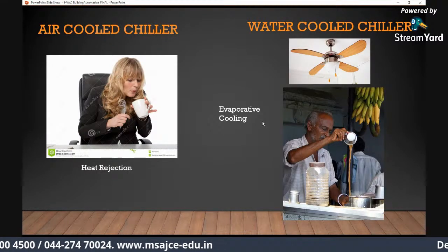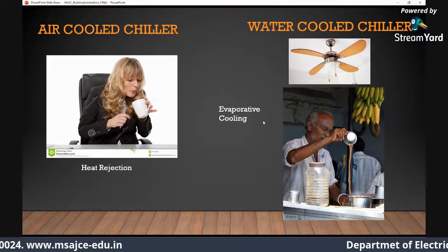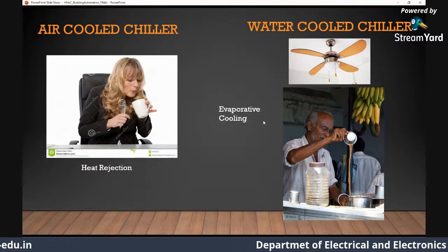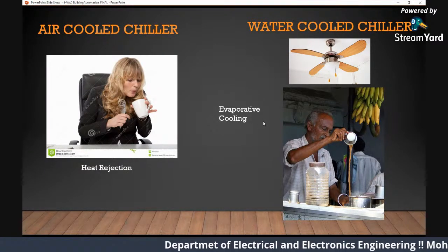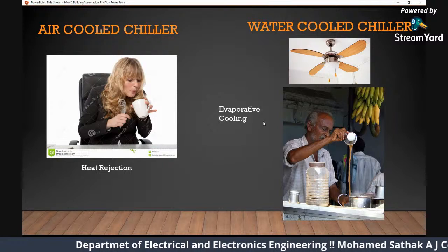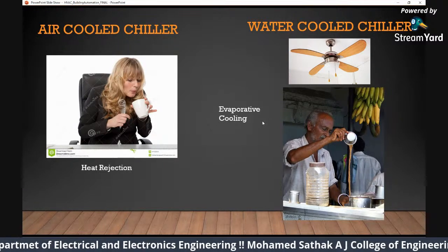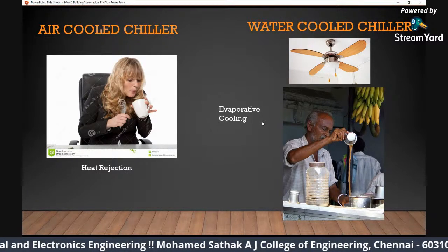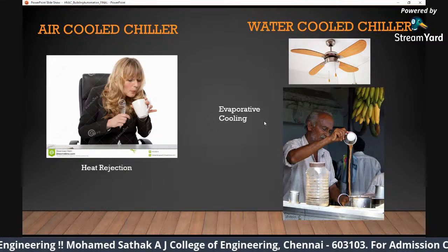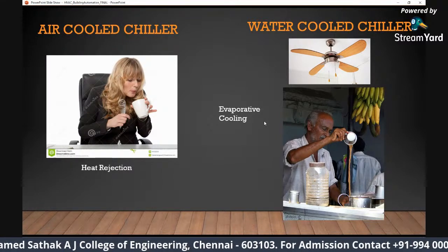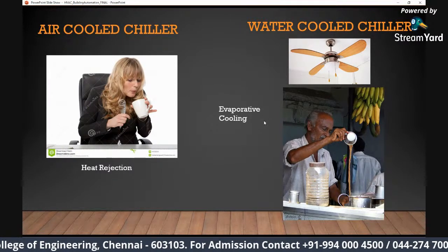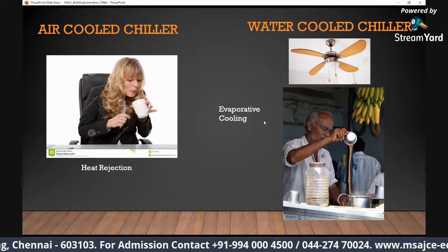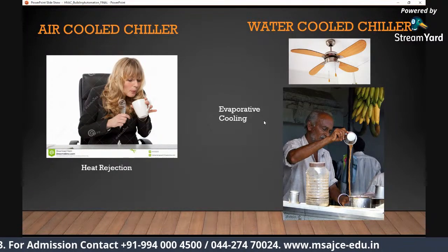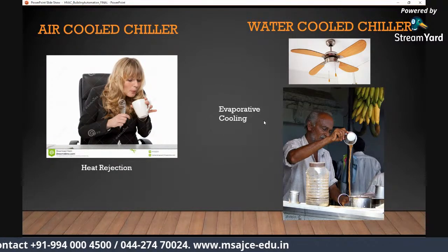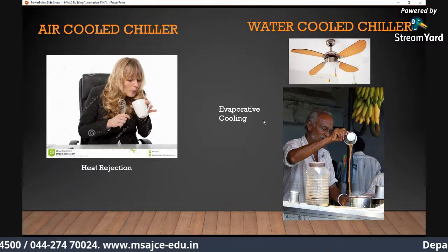Now let's say water cooled chiller. This is the evaporative cooling method. What happens? The water from the condenser goes to the top of the cooling tower and it gets poured. And there's a cooling tower fan. You might ask, there is a fan on both the air cooled and water cooled chiller, but here there is no water. So that's a major difference. There's cooling tower water which goes to the top of the cooling tower. The fan keeps rotating and the water gets sprayed down so that the heat is rejected. We call it evaporative cooling.